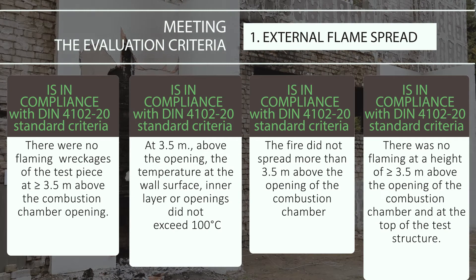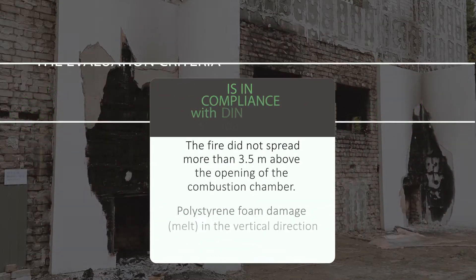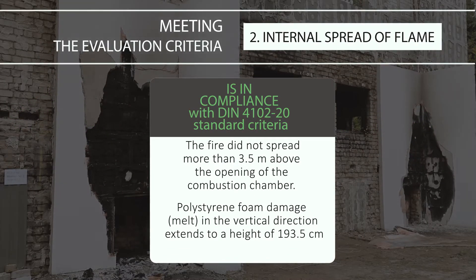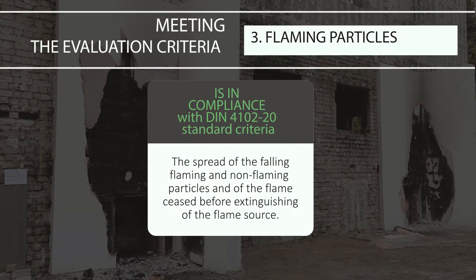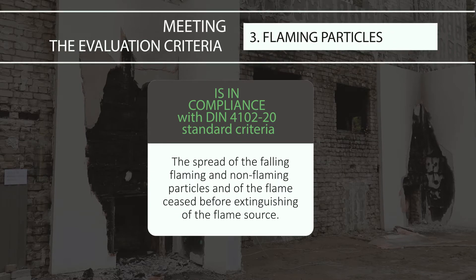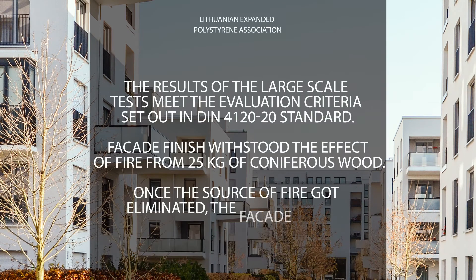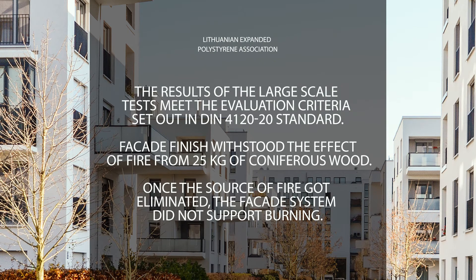The findings of the evaluation of both test pieces with regard to external and internal spread of flame were in compliance with the criteria set out in DIN 4102-20 standard. The results of the large-scale tests met all evaluation criteria set out in the German standard method DIN 4102-20. The facade finish withstood the effects of fire produced by 25 kg of wood.